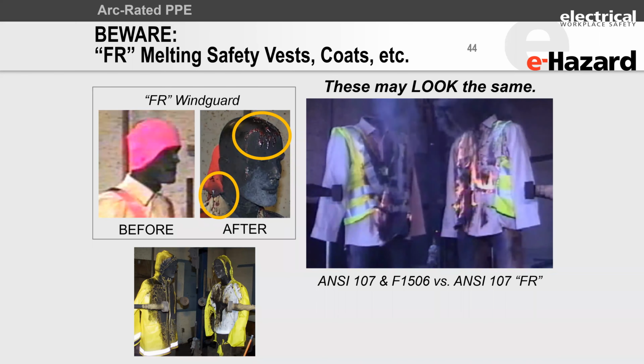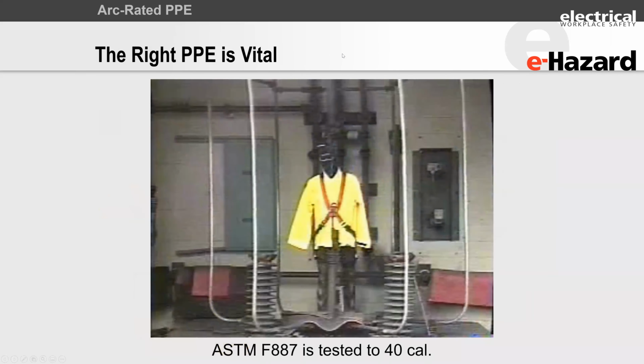Making sure you're not just wearing old FR, flame resistant gear, but actually wearing something that has an arc rating or a flash fire rating. That makes a huge difference for the workers.